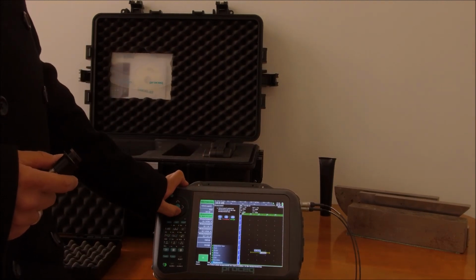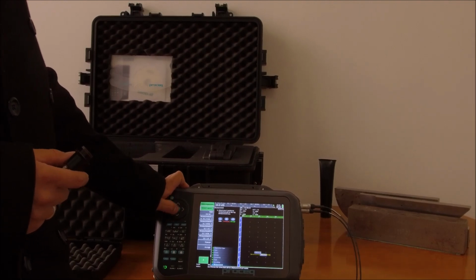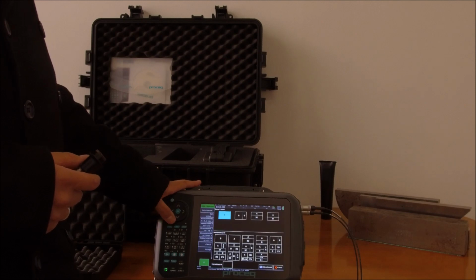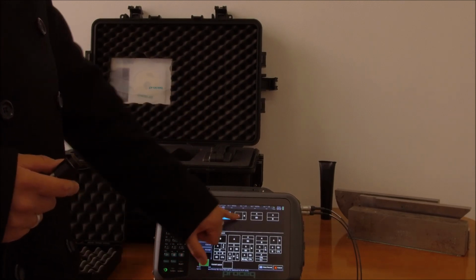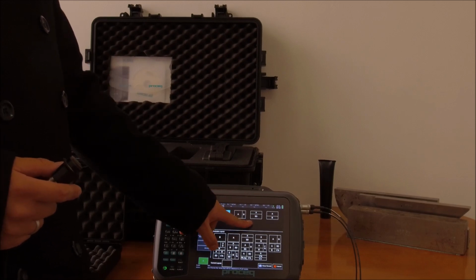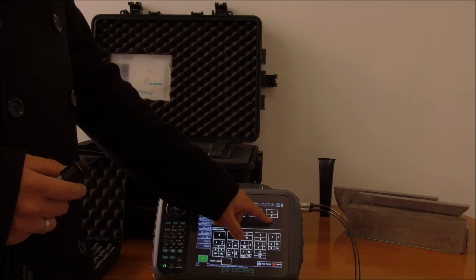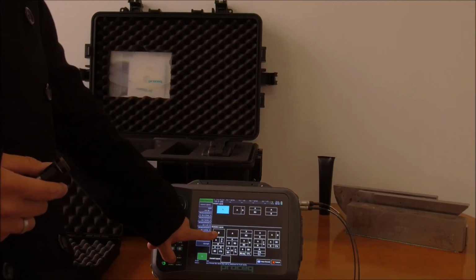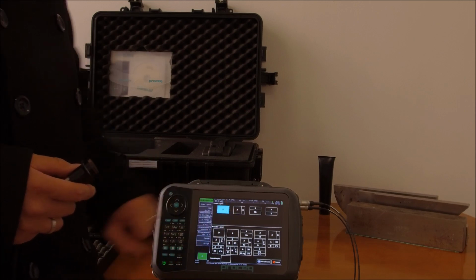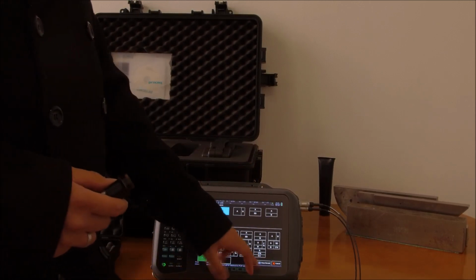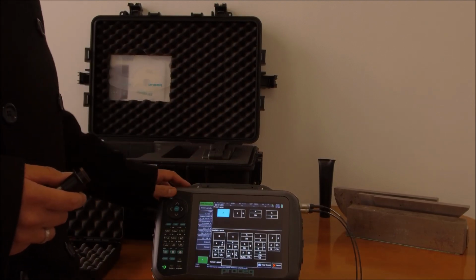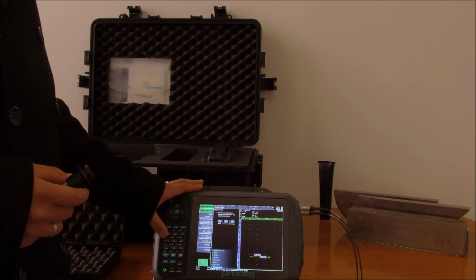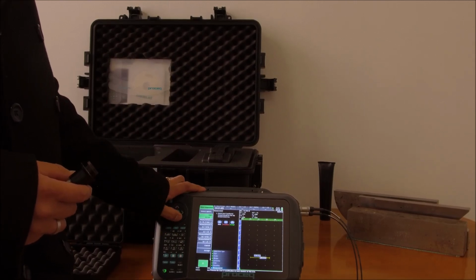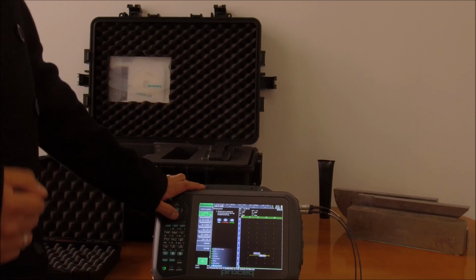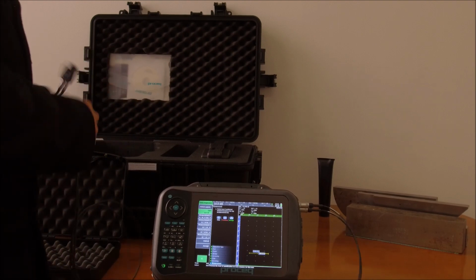Okay, then we come to this last setup. So there's a couple of things that we can nominate. We can select a layout, so we have the option of using an A scan with the B scan right next to it, an A scan with a 3D representation right below, an A scan with the B scan on the bottom. We can just look at a B scan. We can have, there's all sorts of things that we can do here. C scan based on percentage, C scan based on depth, all that good stuff. So you just choose the one that you think would be best for you. In this instance, I'm just going to stick to an A scan. Okay, then we can set our starting gain. So at this point, I'll just go and grab my standard V1.